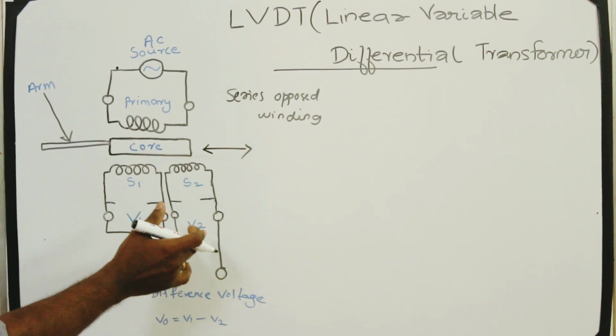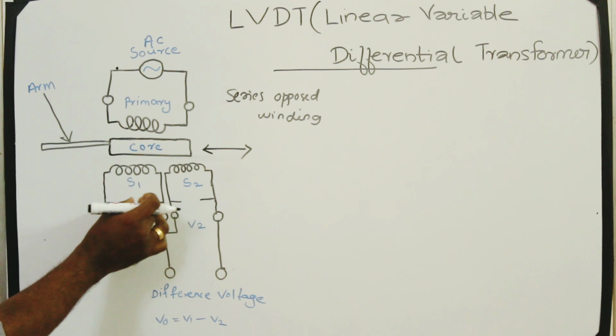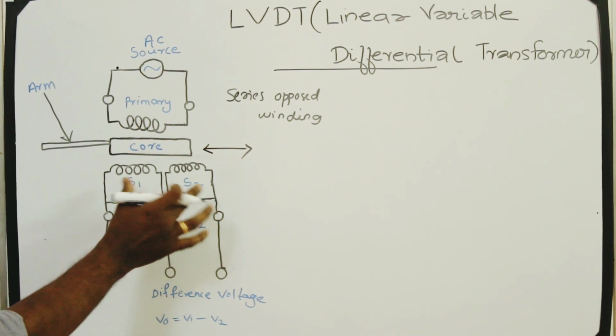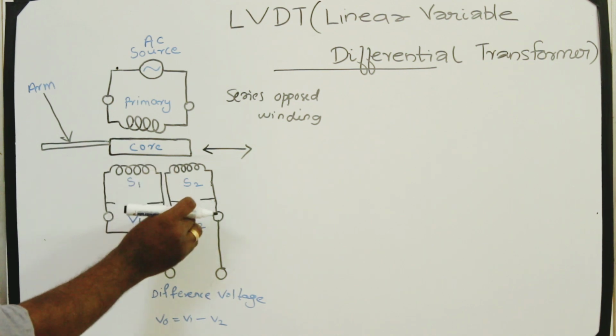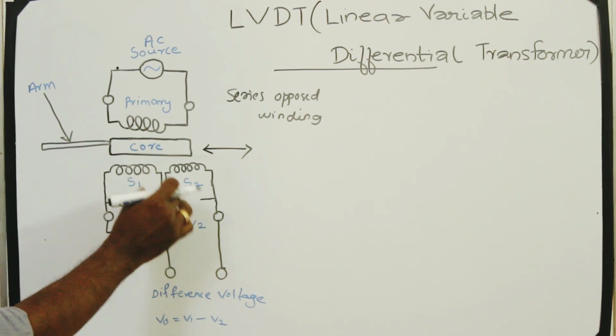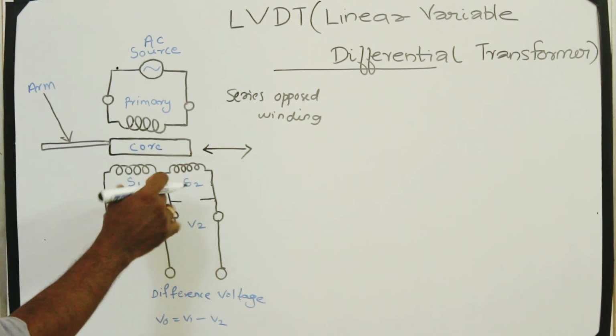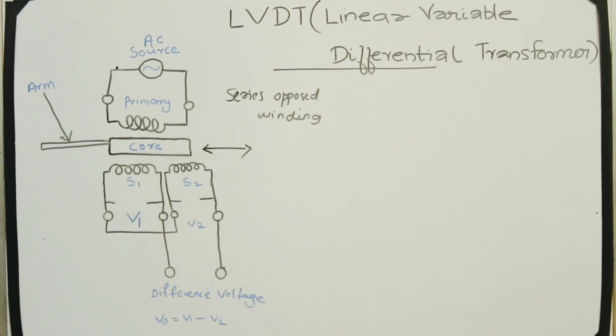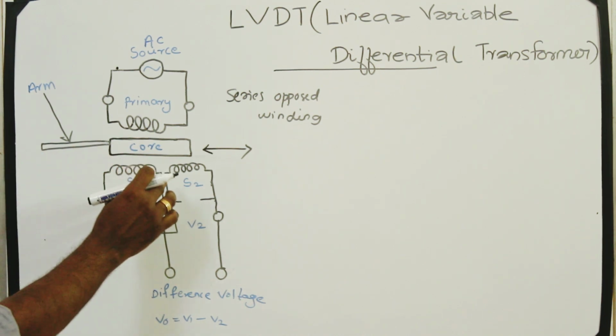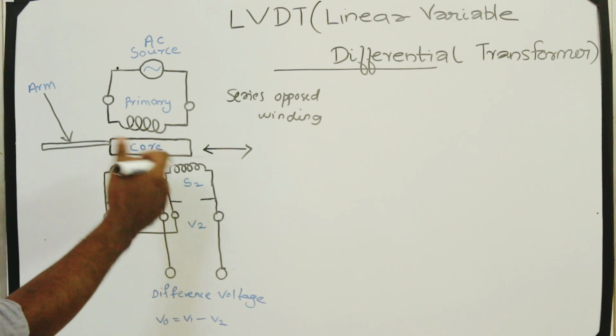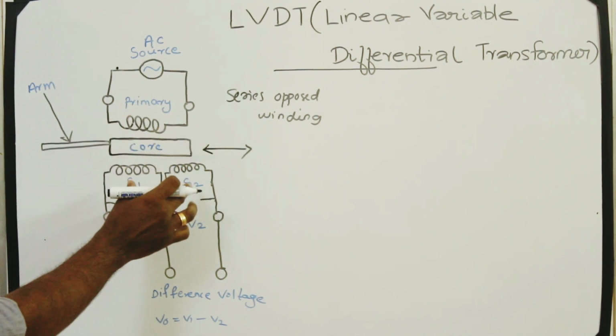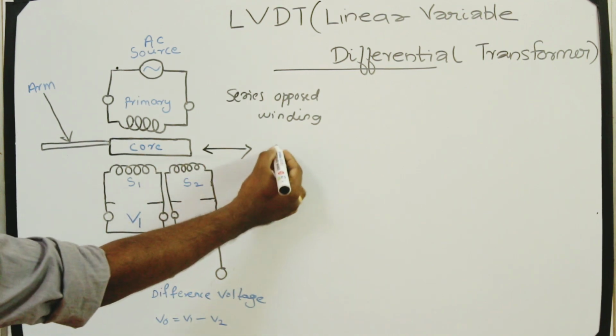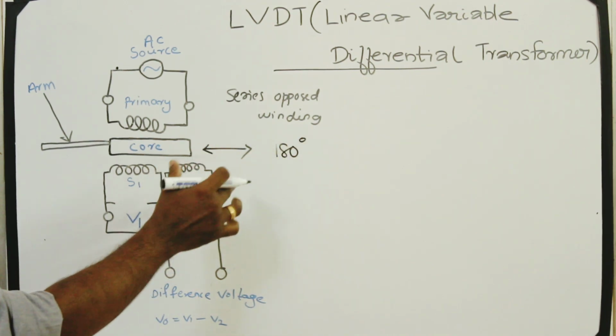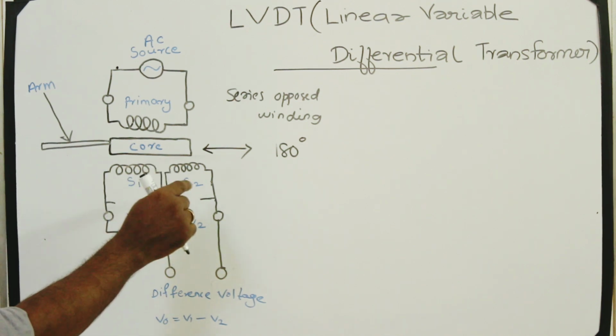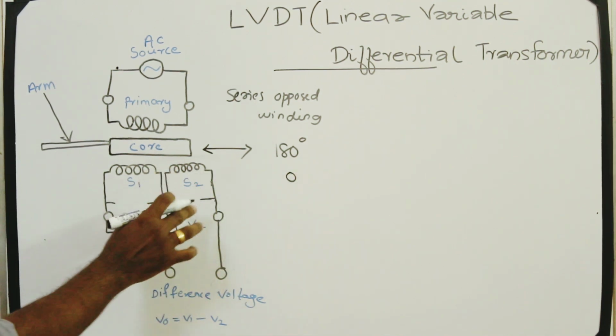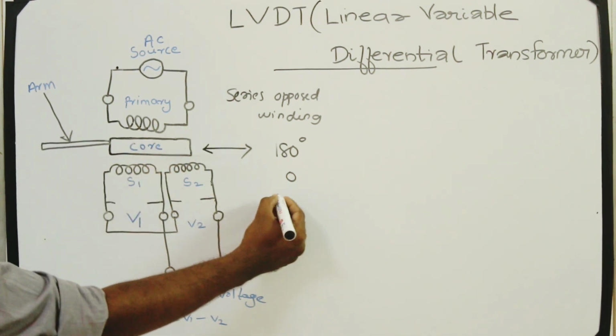The differential voltage in the secondary windings determines the distance moved, and the phase of the voltage indicates the direction of the movement. The series opposed winding of the secondary coil means that when the core is at the center of the transformer, that is equidistant between the two secondary coils, the induced voltages have an equal amplitude but are out of phase by 180 degrees. Thus, the induced voltages cancel each other and the output voltage is zero. This is often referred to as the null point.